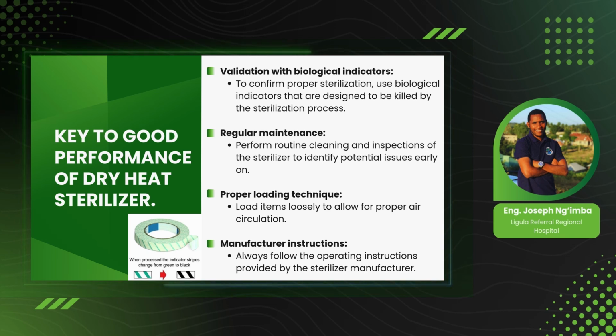Also, proper loading of the item will help us to reduce problems arising from improper loading. For example, temperature inconsistency due to blockage of circulation. Maybe we found the user loaded the item up to the fan, so the fan won't be able to circulate the temperature. So it is important to check the proper loading. And for us that work in the hospital, we'll have to remind the users about this part of proper loading.